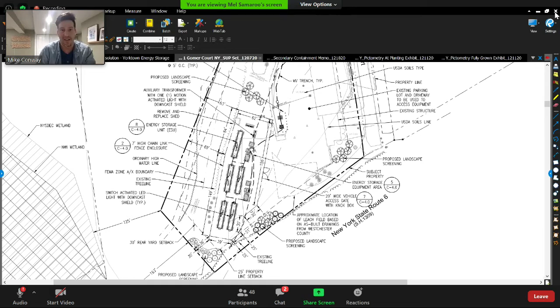Sure, let me share my screen again. Mel, while you're pulling that up, I'll describe the transformer/substation question. Because the interconnection voltage on this project is relatively low on the medium voltage spectrum, there's no full substation required for this. We will be using 2 separate transformers to step up to the voltage at which we connect to the Con Ed system. Those are 2 of the boxes included in what's termed the energy storage equipment area.